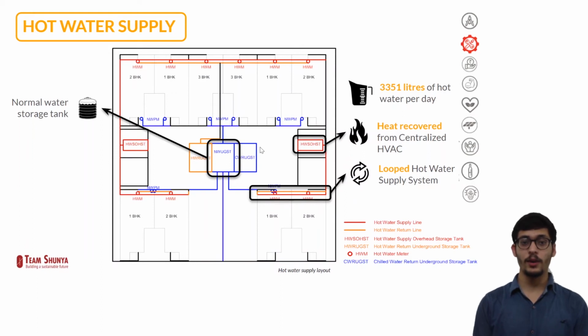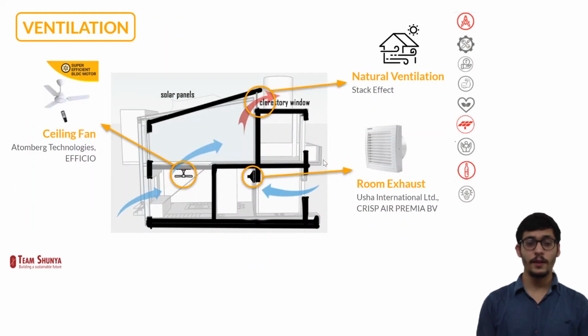The energy needed for heating the water is tapped from centralized HVAC. We have used a looped hot water system which reduces the wait time and water losses. The ventilation requirement is calculated as per ASHRAE 62.2/2019 version. For enhancing natural ventilation effect, the passive strategy of stack effect is used along with spot ventilation technique. Ceiling fans are installed to operate along with radiant panels for better circulation of indoor air.